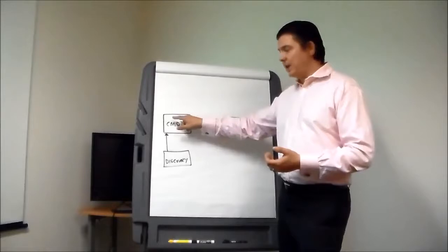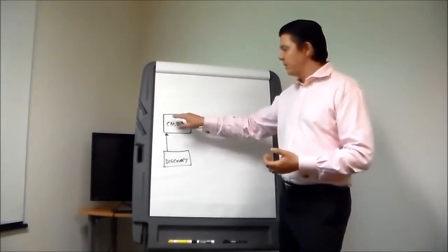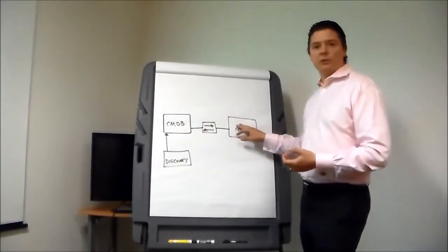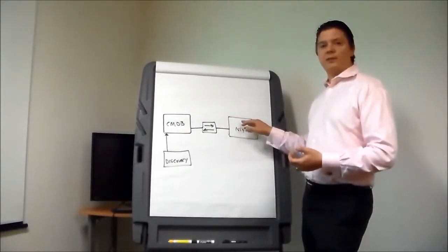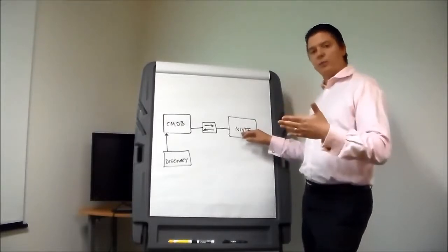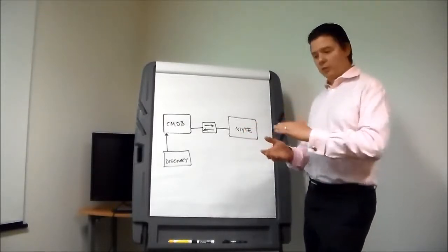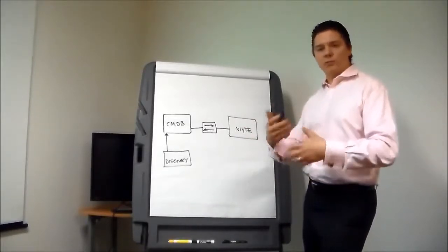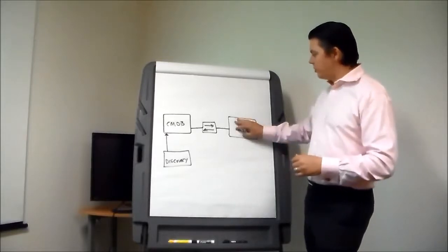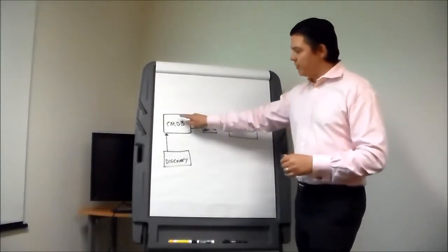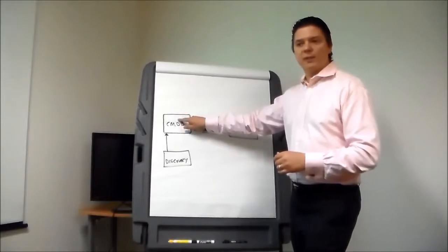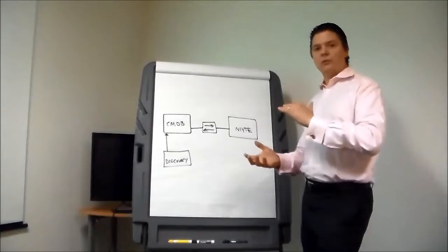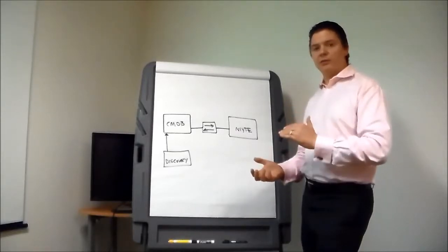Now, coming back to that, inside the CMDB they'll say this is a DL380. Inside Nlyte, we have a material which is a DL380, which has a detailed picture of exactly what it is: its U positions, the capacity that it takes, the amount it weighs, its overall heat and everything else. So we store that inside Nlyte. Within the CI, you'll just get a manufacturer and a model. We extend that out to be more detailed: what does that actually mean? What's the capacity it actually takes?